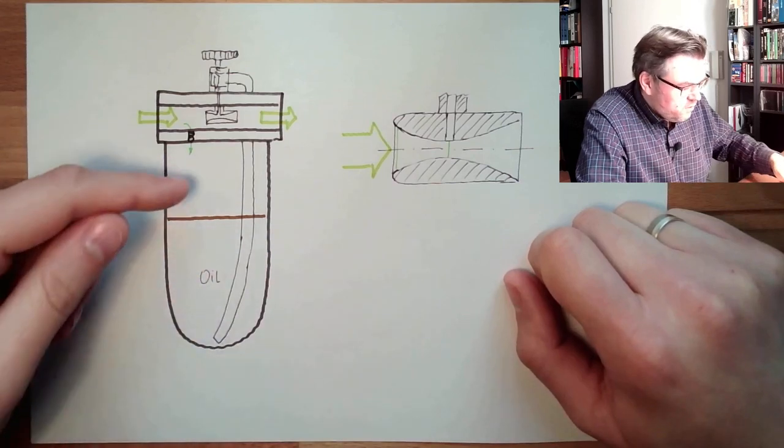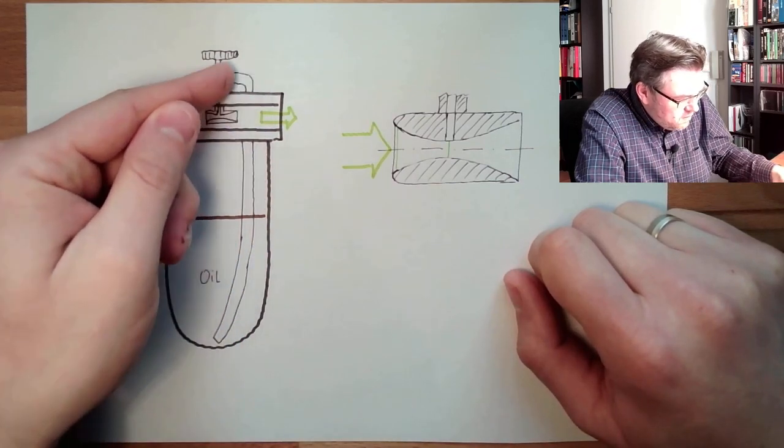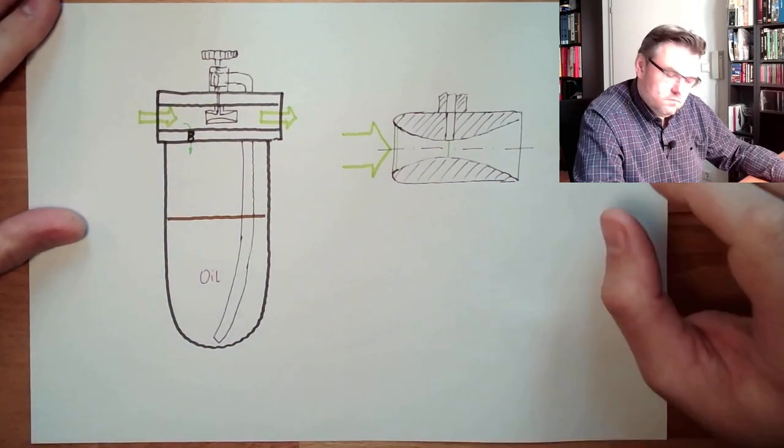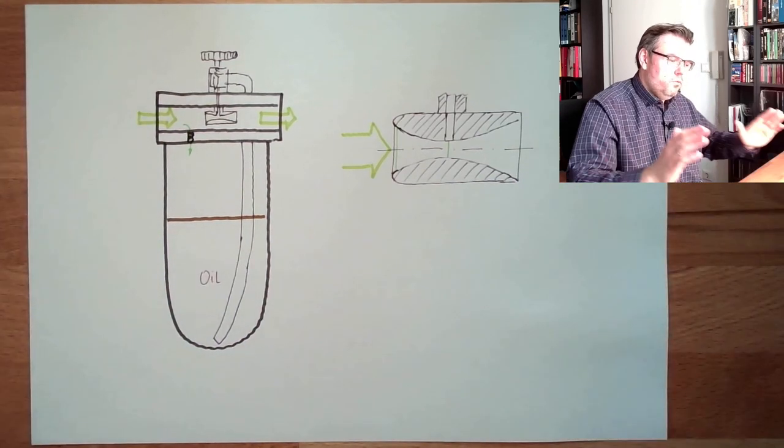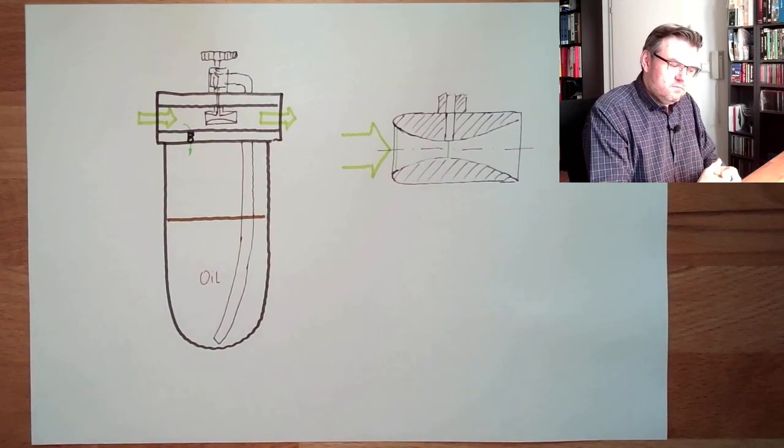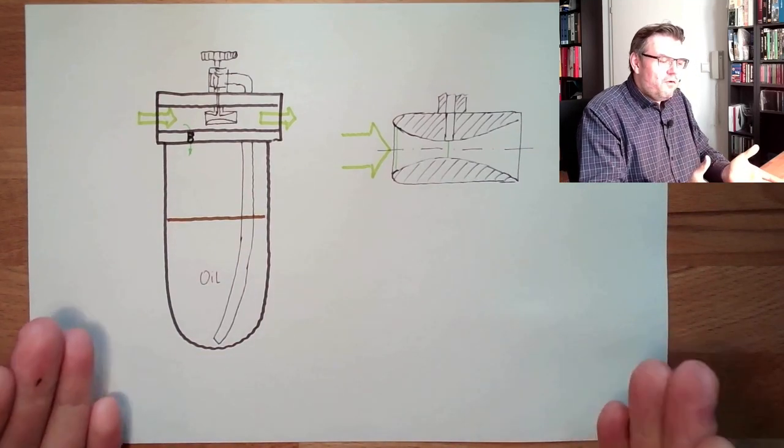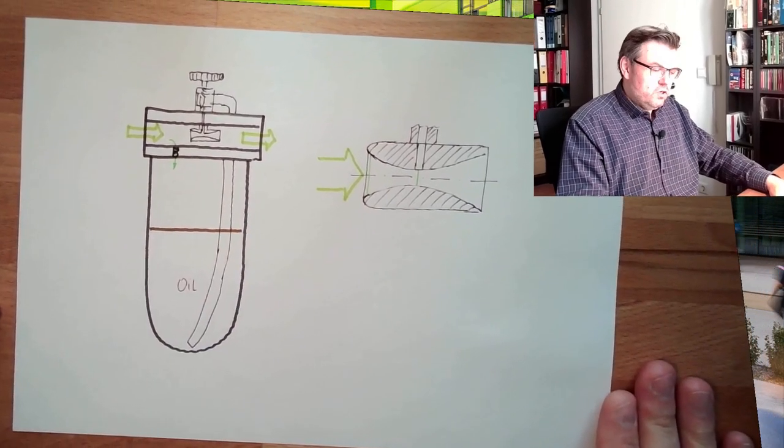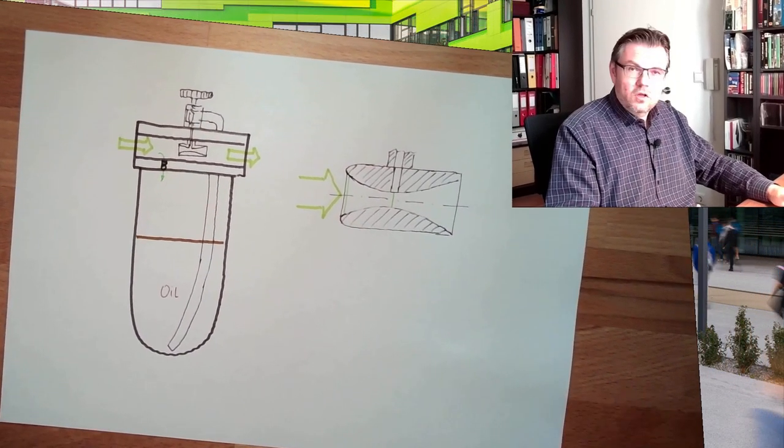Of course we need the energy to lift the oil. This energy is coming from the air itself. So there is no extra energy needed. We just take it from the process. This is how an oiler works. Venturi principle. Interesting thing. So oilers.